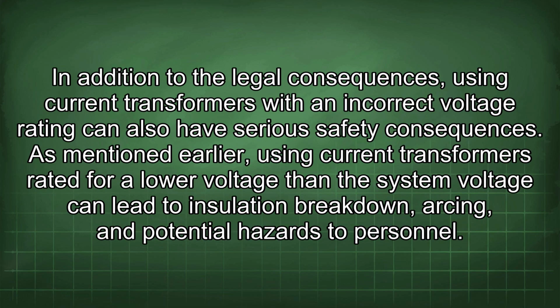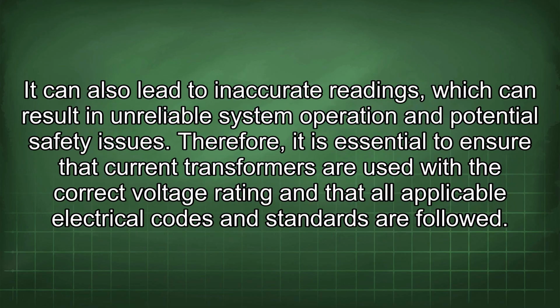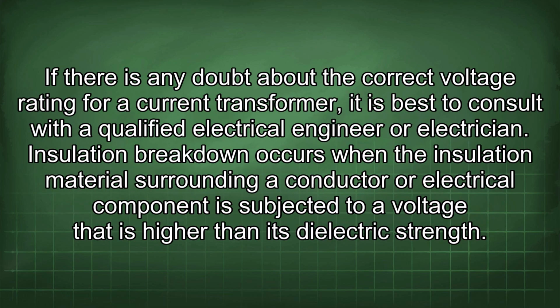In addition to the legal consequences, using current transformers with an incorrect voltage rating can also have serious safety consequences. As mentioned earlier, using current transformers rated for a lower voltage than the system voltage can lead to insulation breakdown, arcing, and potential hazards to personnel. It can also lead to inaccurate readings, which can result in unreliable system operation and potential safety issues. Therefore, it is essential to ensure that current transformers are used with the correct voltage rating and that all applicable electrical codes and standards are followed. If there is any doubt about the correct voltage rating for a current transformer, it is best to consult with a qualified electrical engineer or electrician.